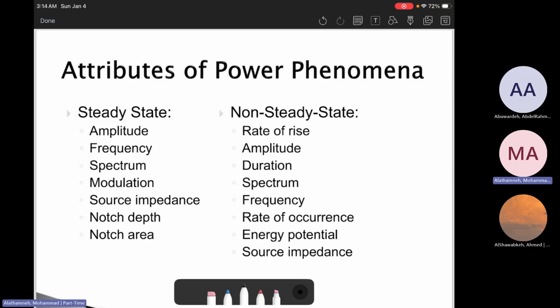Or it can be non-steady state, which is something temporary, like the rate of rise, how fast the transient goes, and the duration, is it within milliseconds or within seconds. The frequency content, is it oscillatory or just an impulse happening once and disappearing, or oscillatory and degrading with time. The rate of occurrence, is it rare, is it frequent, is it happening multiple times a day? And the energy potential, how much energy is there, to monitor the damage capability, is it going to cause big damage or not?